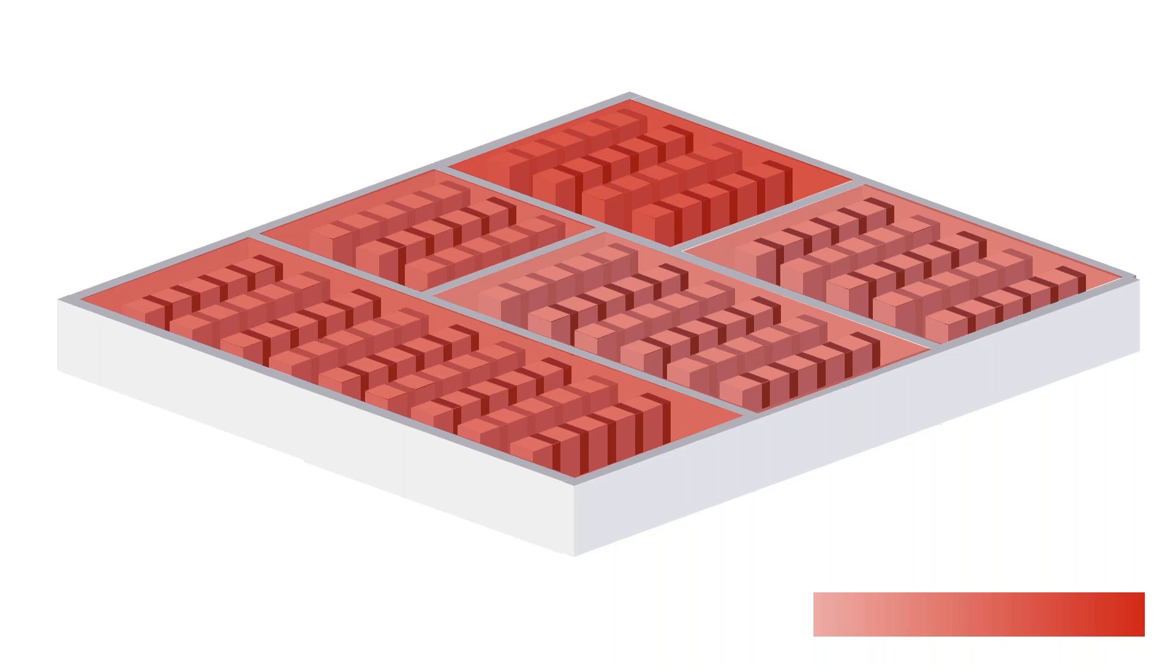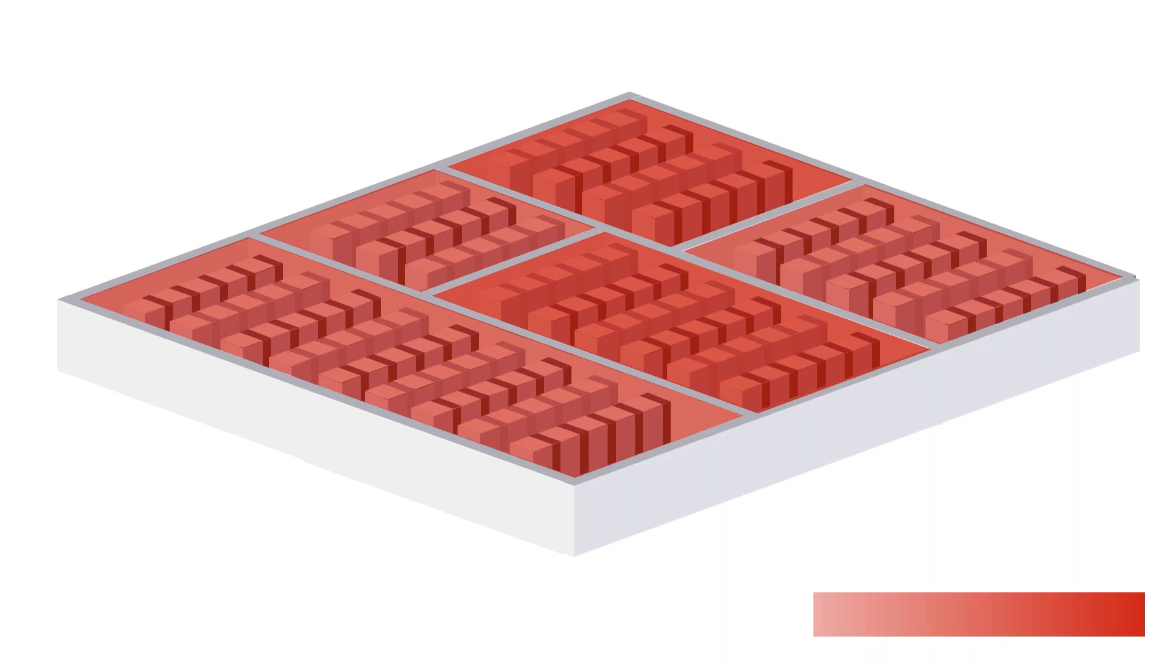They're shifting massively, and if you run a co-location type facility you have customers saying, hey I have super heat dense computers, are you able to cool them? This puts us in a space where the idea of using pressure independent control valves gives us a lot of flexibility. The reason pressure independent control valves are so valuable in commercial HVAC is they take all the nonsense out of cooling a building. Loads shift up and down, people come in and out, equipment turns on and off, the sun's shining or not.